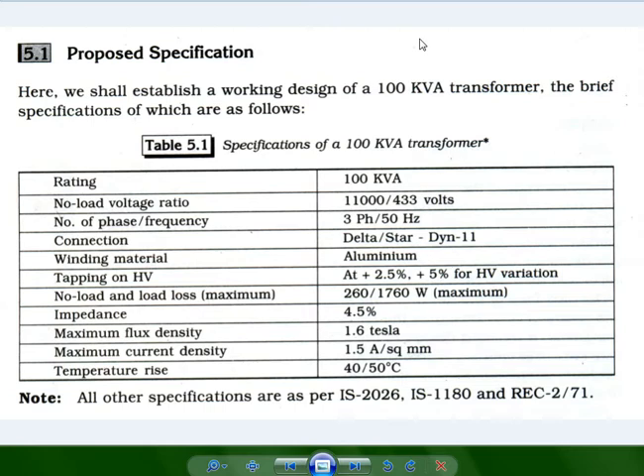50 degree centigrade is the internal winding temperature, maybe the internal low voltage winding. So there will be a 10 degree gradient between the inner side of the transformer, or the limb of the transformer, where it's going to be 50, so you have to cool down the transformer tank in such a way that it is 40.